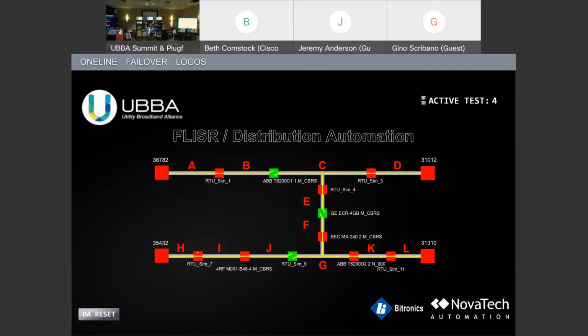We might just have one or two customers off. That's great on a normal day. If the wind starts blowing and you do that, though, you would blow fuses all over your system, and you would have to go out and repair a bunch of fuses. In that situation, we're on the other side of the equation, and it's better we put it in fuse saving mode when a storm's coming.